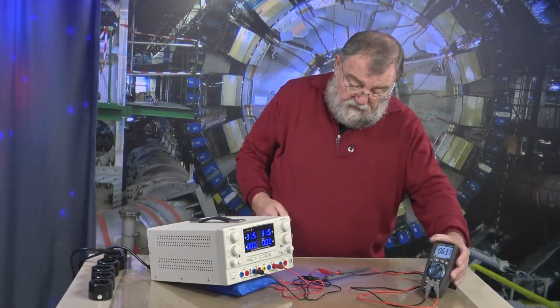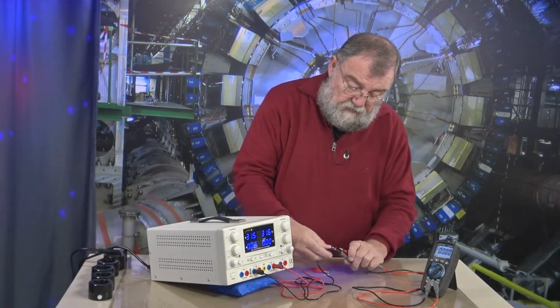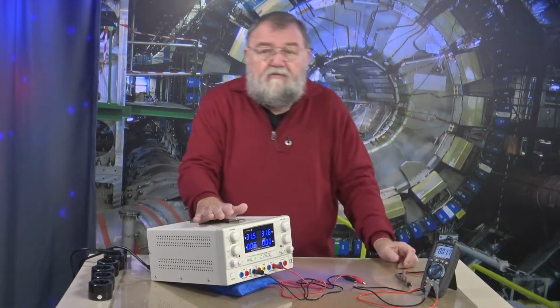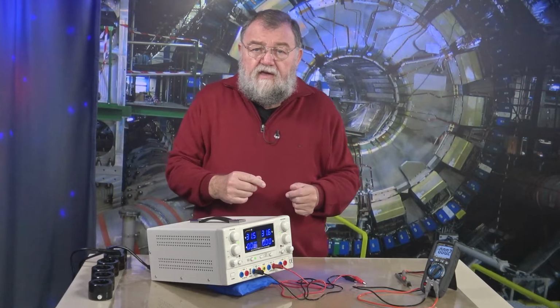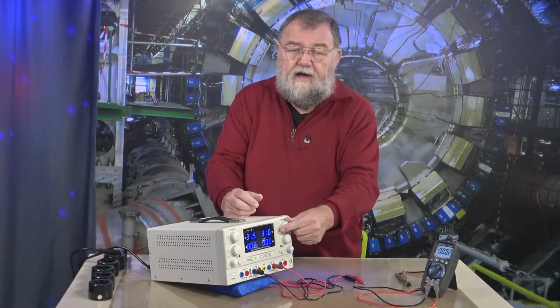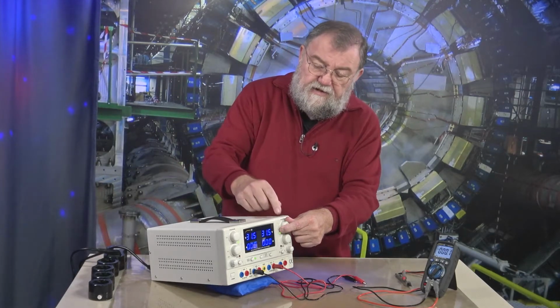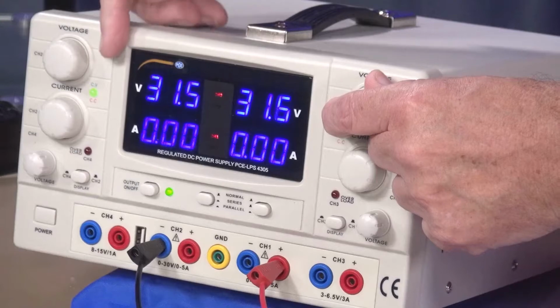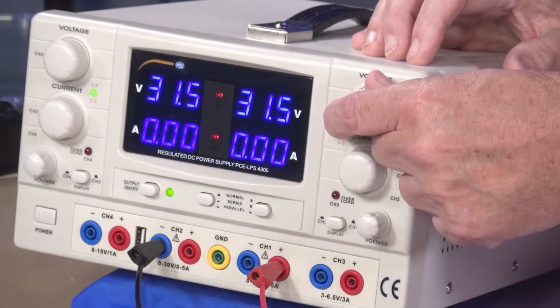So just take these back off. Now we have the possibility to switch both main power units in a row to make the out voltage double. I don't have to turn two wheels, just turn one, and through the tracking mode both power units are set to the same value.